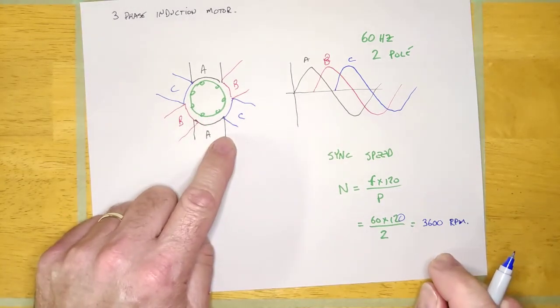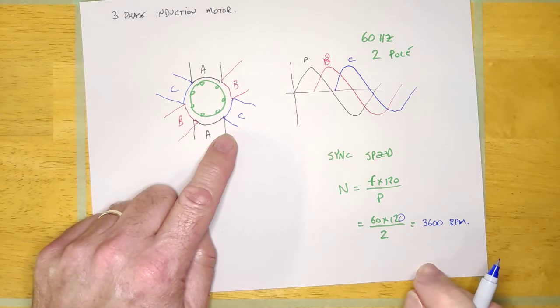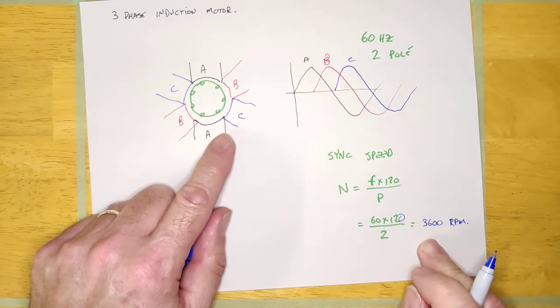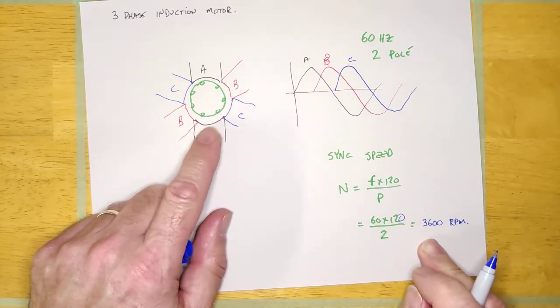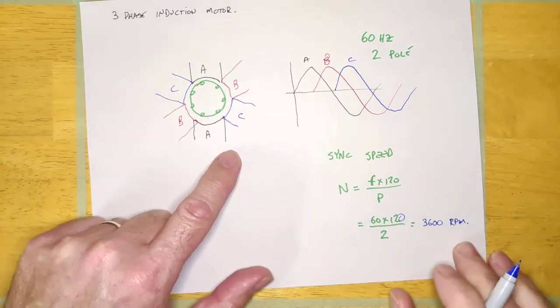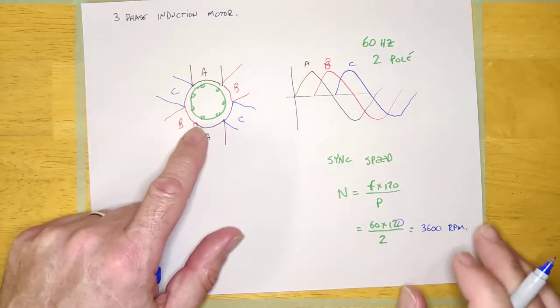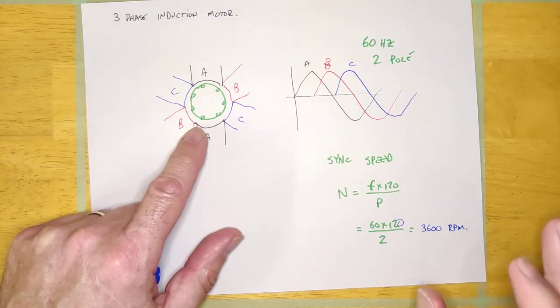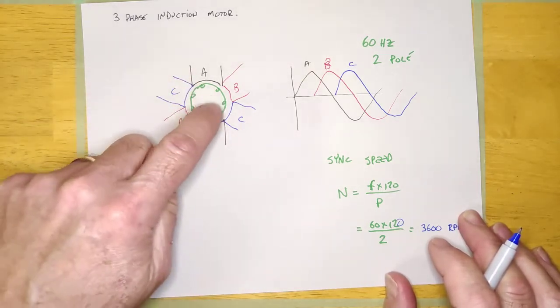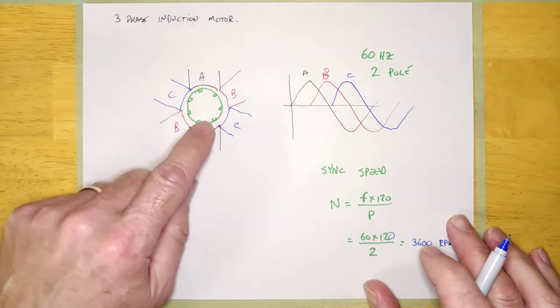This machine has a sync speed of 3600 RPM, same as a three-phase two-pole motor. There are really only two common types of induction motors: one that runs close to 3600 RPM because it's a two-pole, and one that runs close to 1800 RPM because it's a four-pole. Six-pole motors exist but are pretty rare. A two-pole motor will show something like 3500 or 3450 RPM on the nameplate depending on the motor.